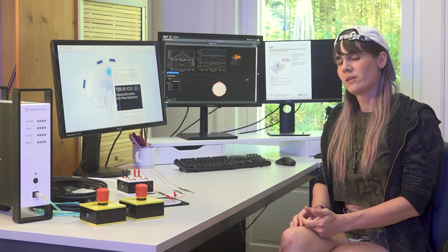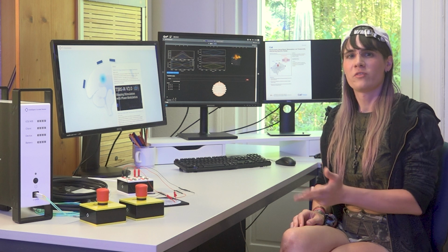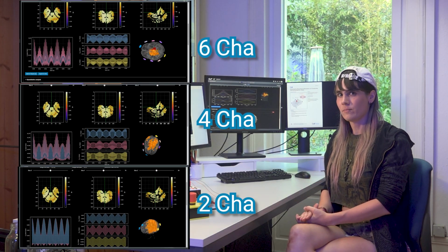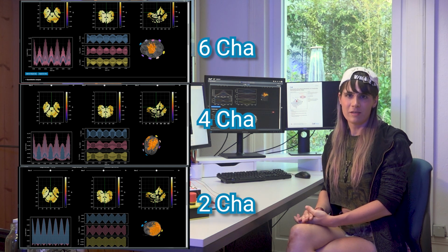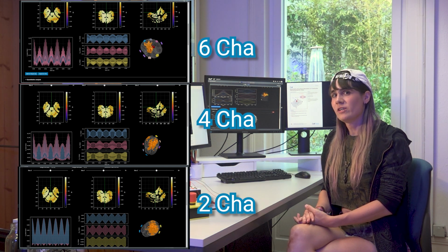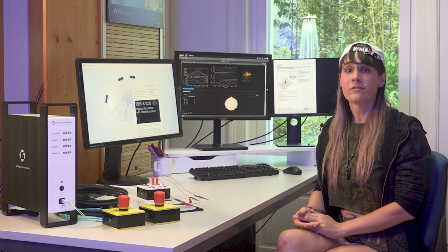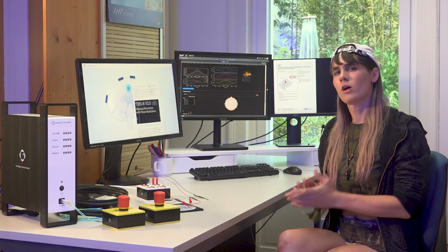Having more than 2 channels has the following substantial advantages. First, you can improve focality and stimulation selectivity, and even achieve multifocal stimulation. And second, the currents are distributed over larger scalp surfaces, and therefore current densities and the risk of associated confounding sensations are reduced.